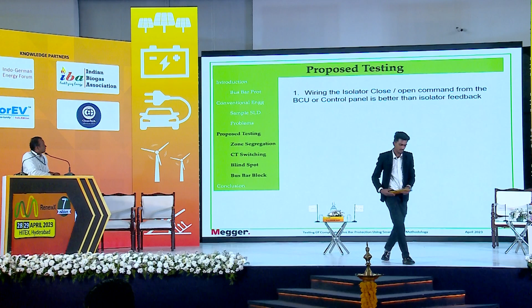So these are the proposed solutions. So wiring the isolator with close and open command from the bay control unit or from the panel. So this is a very, very important area. Nowadays when we talk about smart grid systems, we have numerical relays with the IEC 61850 principle. So the relays have the capability of transmitting information from one relay to the other using fiber optic cables. So they can communicate. So when the relays are communicating this information, why should we fully be dependent on the cables? So if there is a problem with the cable, we can still get this information through fiber itself. And the relays are kept in the panel itself. So the isolator is in the switchyard.